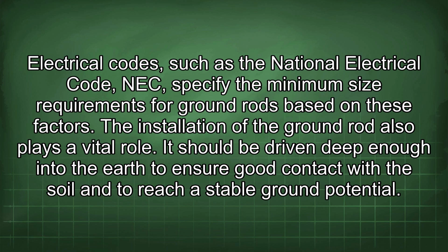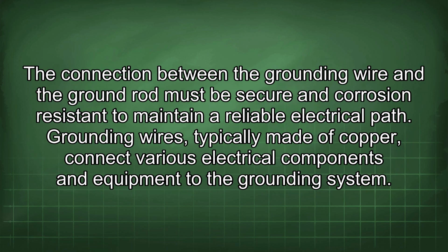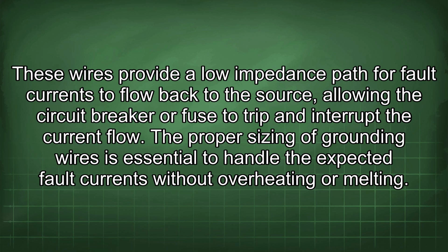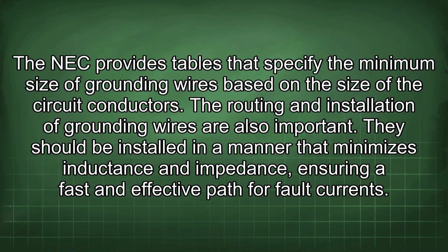It should be driven deep enough into the earth to ensure good contact with the soil and to reach a stable ground potential. The connection between the grounding wire and the ground rod must be secure and corrosion resistant to maintain a reliable electrical path. Grounding wires, typically made of copper, connect various electrical components and equipment to the grounding system. These wires provide a low impedance path for fault currents to flow back to the source, allowing the circuit breaker or fuse to trip and interrupt the current flow. The proper sizing of grounding wires is essential to handle the expected fault currents without overheating or melting. The NEC provides tables that specify the minimum size of grounding wires based on the size of the circuit conductors.